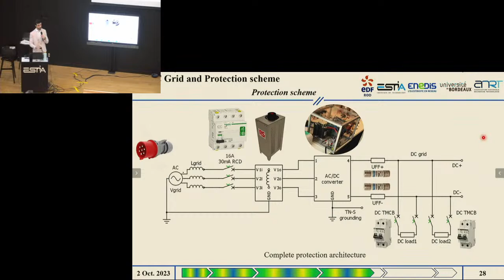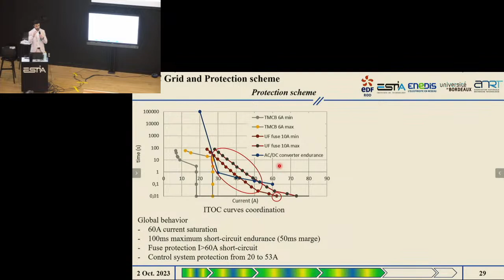And here you can see that since for a current of 60 amps we have a selective point of operation, it is worth choosing this current level to be the saturation current for the current limitation techniques. As you can see here, the converter is able to saturate the current and to limit it to a maximum level of operation of 60 amps, where we are selective, because between the behavior of the converter in blue, the behavior of the fuse, and the behavior of the circuit breakers in gray, we do not have crossing points.